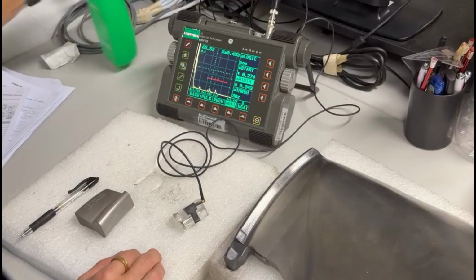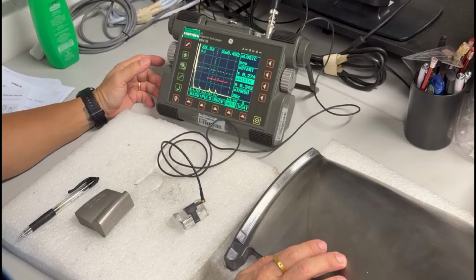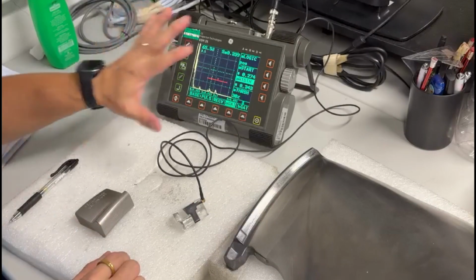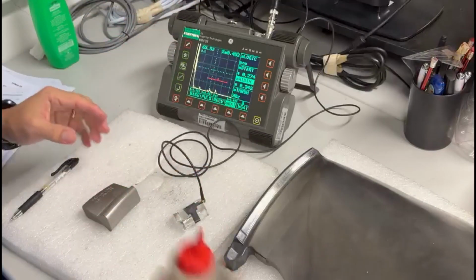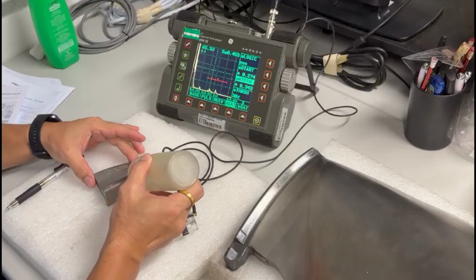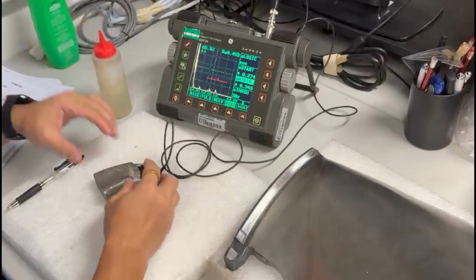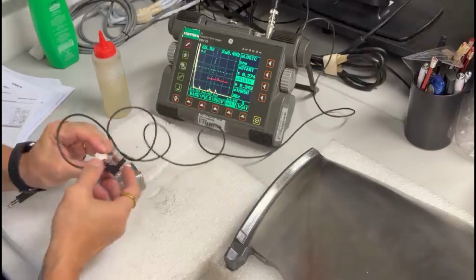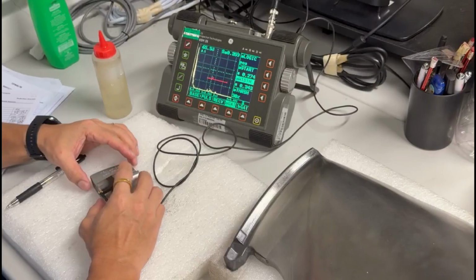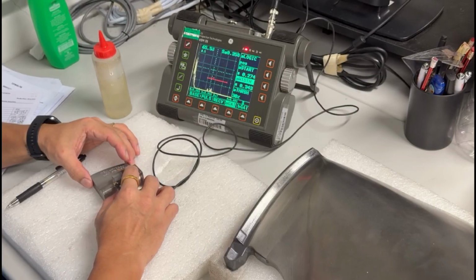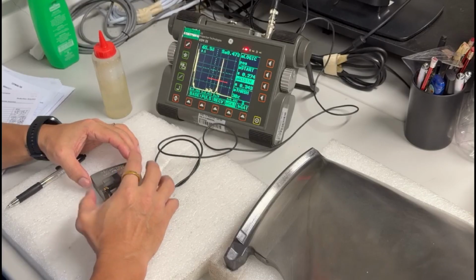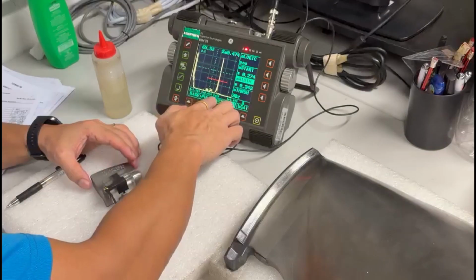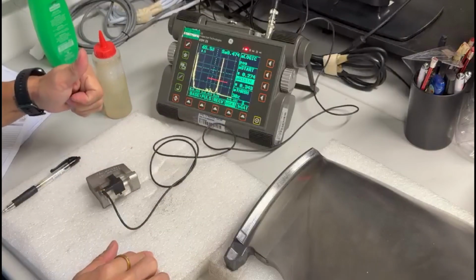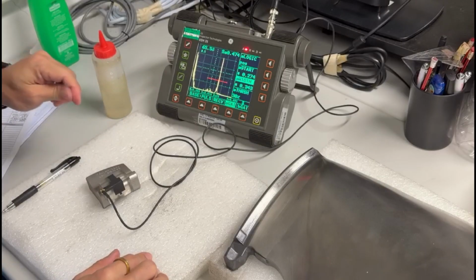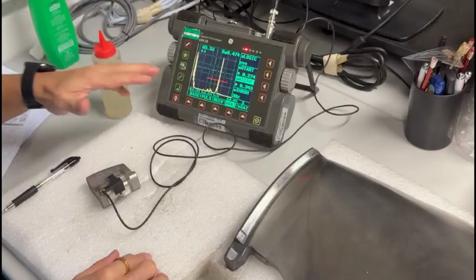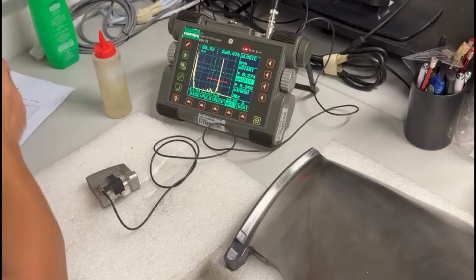Okay, everyone. We completed the inspection of our fan blade. So now we're going to do a post calibration. Nothing changes on our parameters or our setting. Go back to our cal block. Apply couplant again. Then signal. That's it. Still 80%. So we're good to go. No need to do anything because the signal doesn't decrease by 10% or increase by 10%. No changes. So that's it. We're all good. Everything completed.